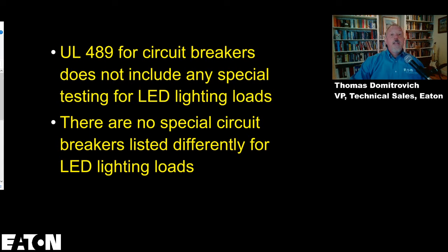LMNOP products. The other thing, as I'm looking for this, the other thing to remember too, we do sell high magnetic breakers. Remember, I could have a breaker that has a higher magnetic, that as long as it's say SWD rated, or it doesn't even have to be SWD rated in the case of LED lighting, but a high magnetic pickup could help you live through that as well.